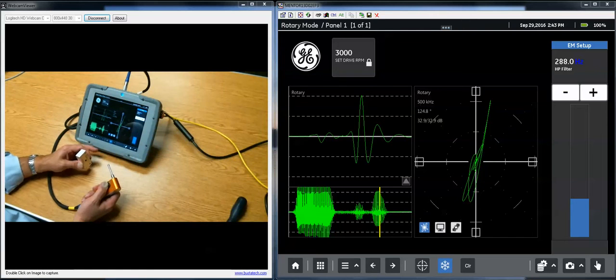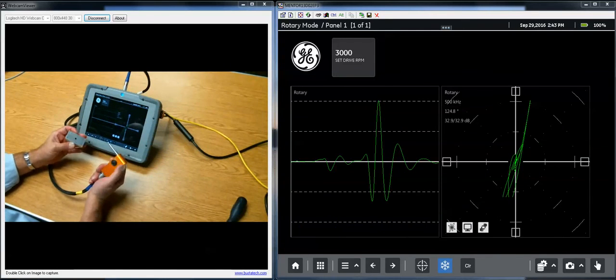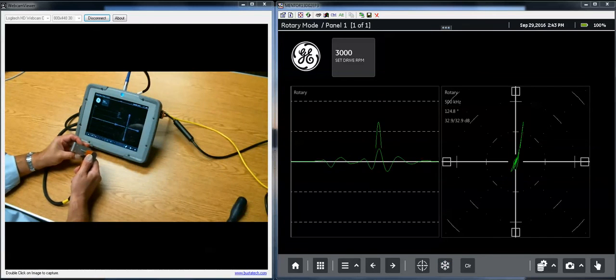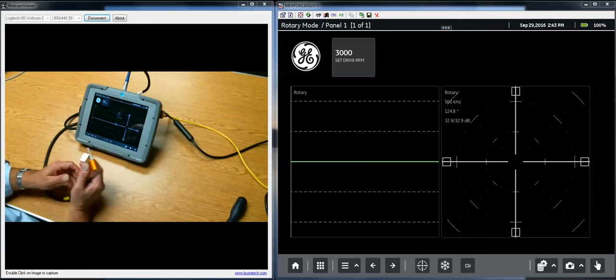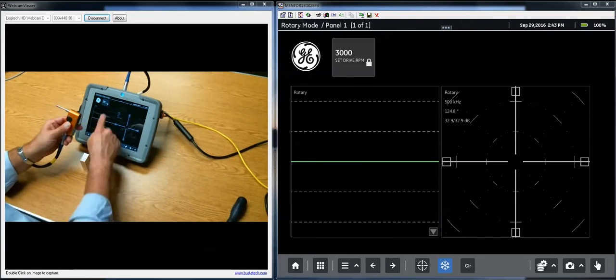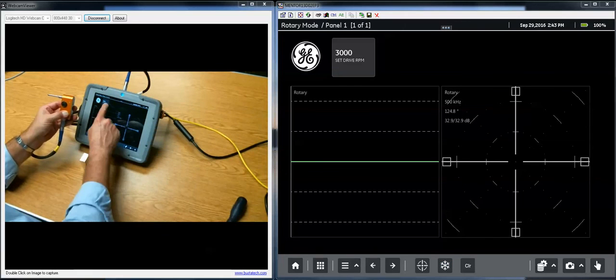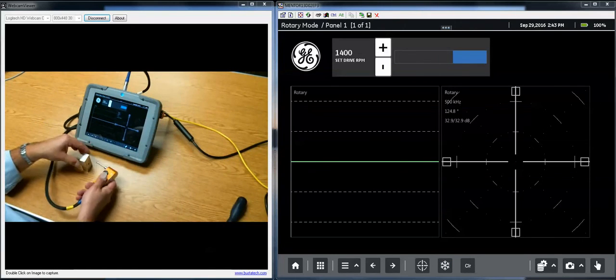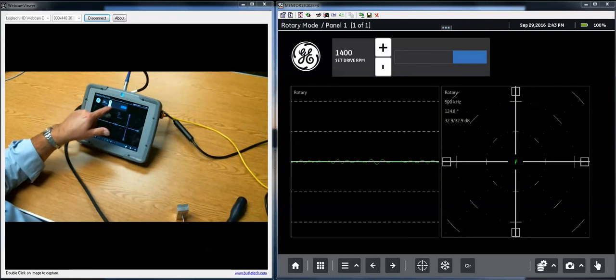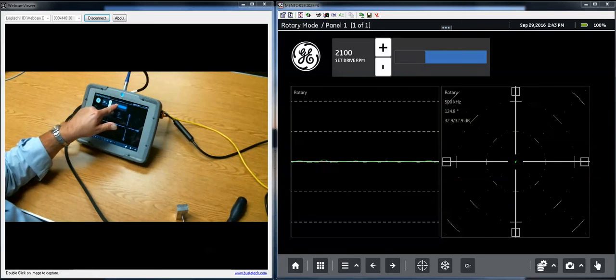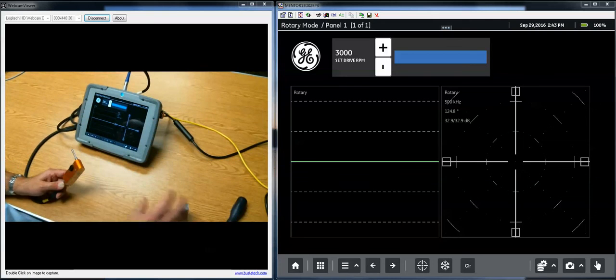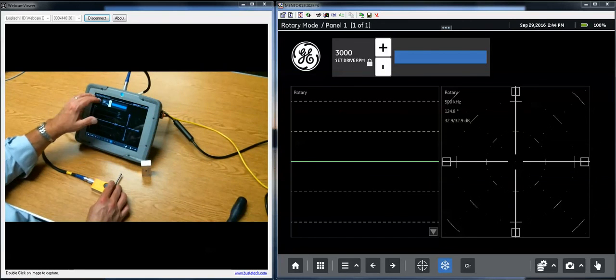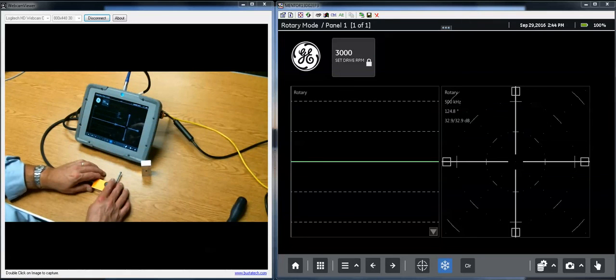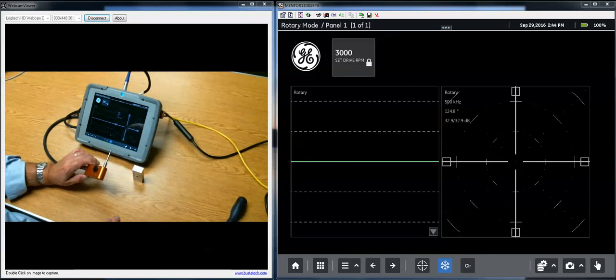At any point, if we're happy with our setup, close our menu, we press the button again, probe begins to spin, and we can make adjustments. Okay. While the probe is spinning, you notice when I have the probe frozen, I can't adjust my speed. Start the probe spinning. I can slow the probe down, and I'll put this over here. You might be able to hear the change in speed of the drive. Speed of the drive is closely related to your filter settings, so be careful of that. But that gives you a basic demonstration of rotary bolt hole inspection with Mentor EM.